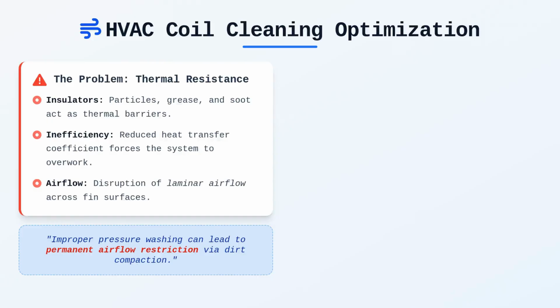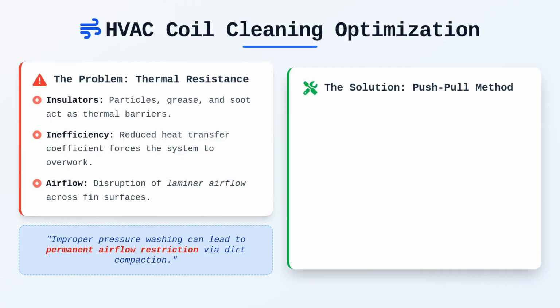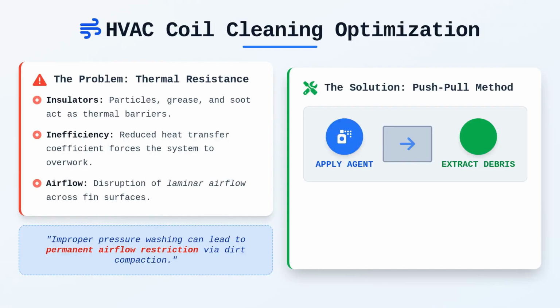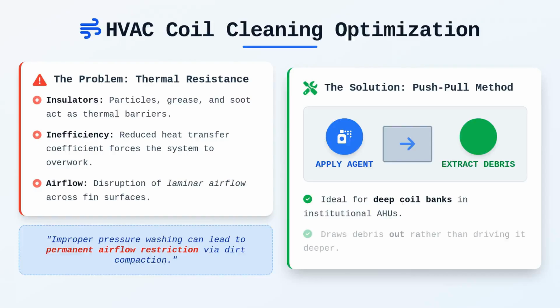When dealing with deep coil banks, such as those found in large institutional air handling units, a single-pass cleaning method rarely suffices. The push-pull method becomes necessary here, where you apply cleaning agents from one side while simultaneously maintaining a vacuum or extraction force on the opposite side to draw debris out, rather than driving it deeper into the fin stack. This technique prevents the compaction of dirt that often occurs during improper pressure washing attempts, which can otherwise lead to permanent airflow restriction.